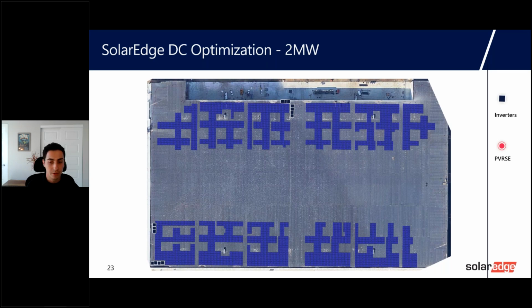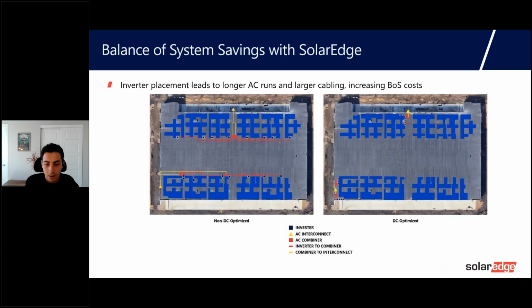And so when we put those two systems side by side, we can see that AC cabling from inverter to combiner and from combiner to interconnect is going to be much more expensive in both material and in labor for a non-DC optimized solution. When we have done an average of this across all the case studies, we've estimated that the AC cabling, conduit, grounding, and install labor account for an increase of 4 to 5 cents per watt on your balance of system costs.